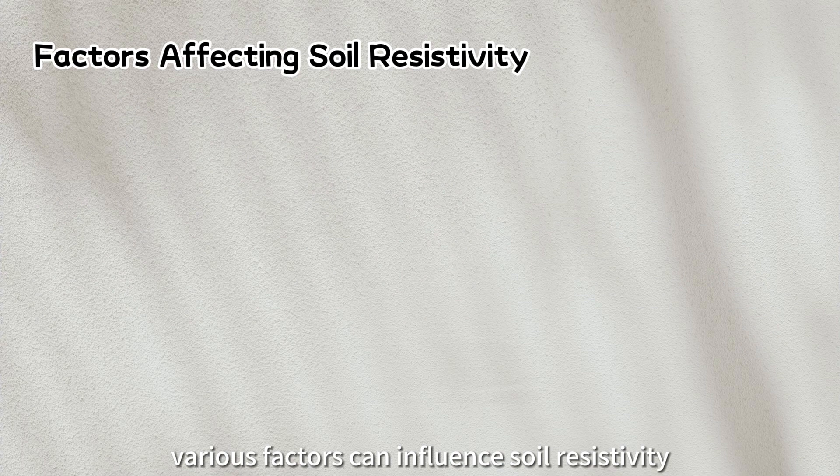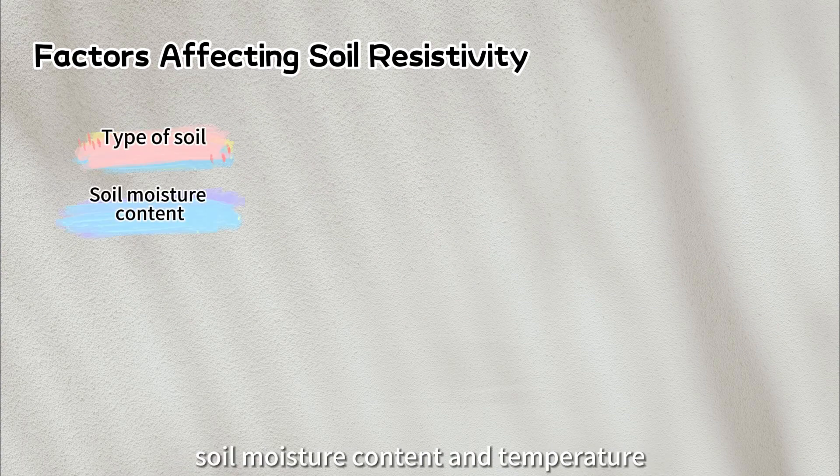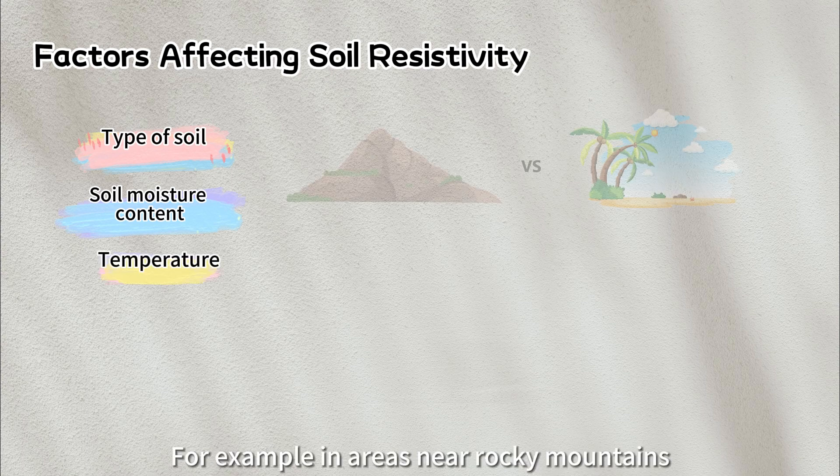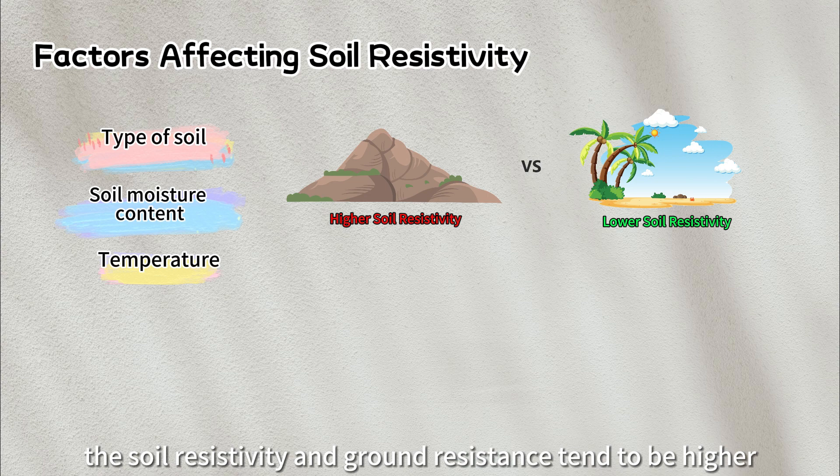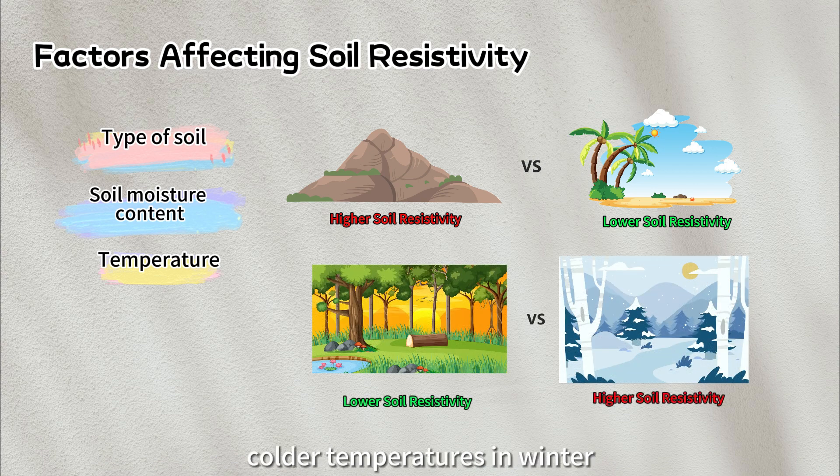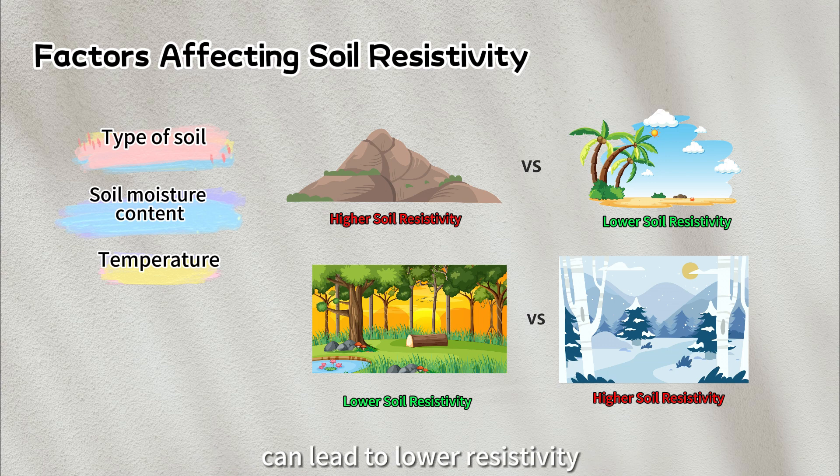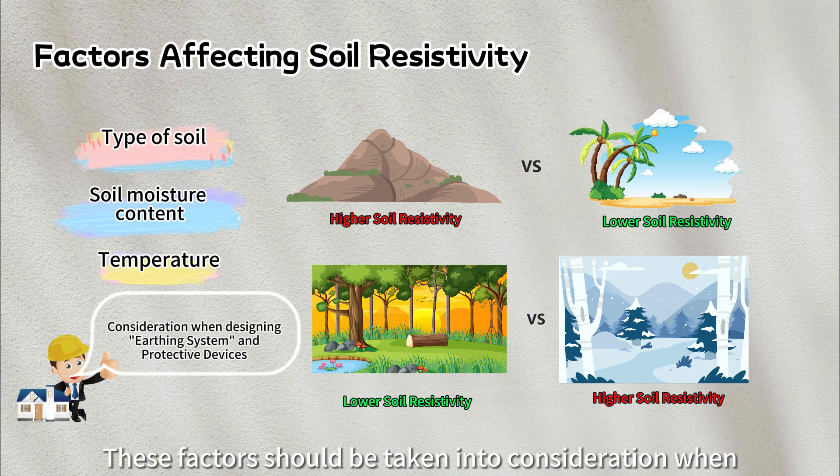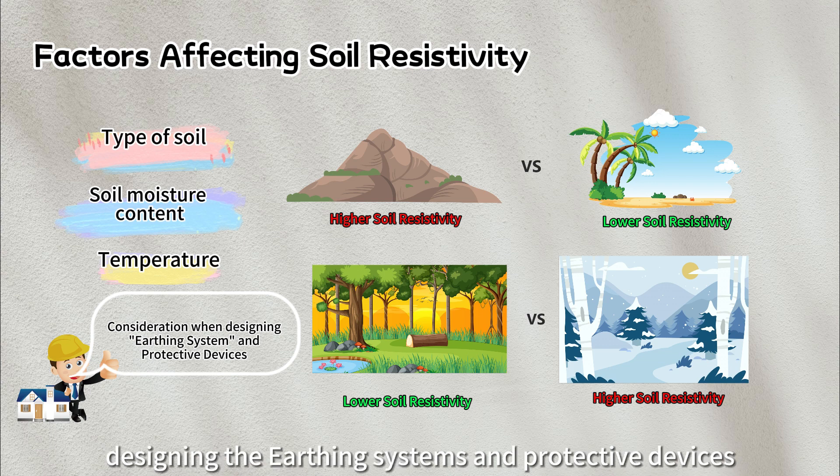Certainly, various factors can influence soil resistivity, including the type of soil, soil moisture content, and temperature. For example, in areas near Rocky Mountains, the soil resistivity and ground resistance tend to be higher compared to areas closer to the sea. Besides, in some countries, colder temperatures in winter tend to increase soil resistivity, while warmer temperatures in summer can lead to lower resistivity. These factors should be taken into consideration when designing the earthing systems and protective devices.